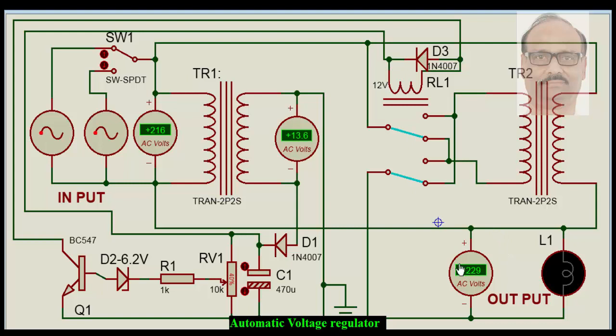While this relay operates, this works like this. When the voltage goes high, this relay changes over to this, subtracting the voltage. From 246 volts, it subtracts this voltage and we get 230 volts.